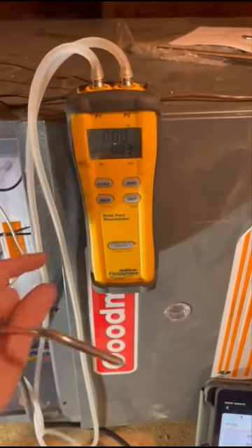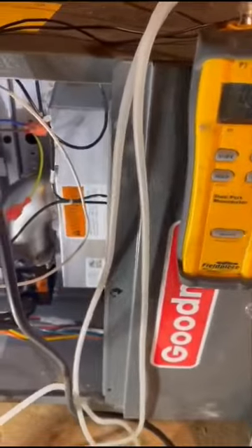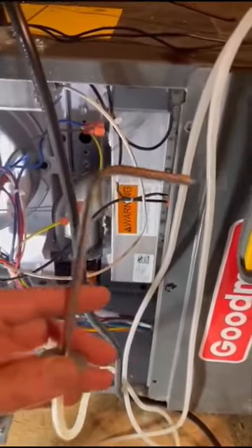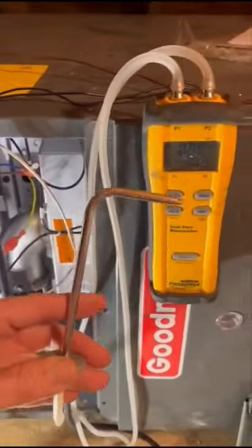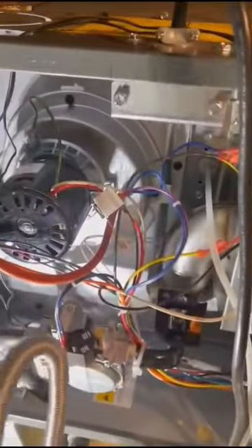Okay, next thing is zeroing out our manometer. Zero, and always the pitot tube needs to sit against the airflow, so the airflow hits the tip of it. That's how it measures our static. So then I remove the high limit switch. Arrow is facing over there. Make sure the high limit is not touching any pieces of metal so it doesn't pop our fuse.